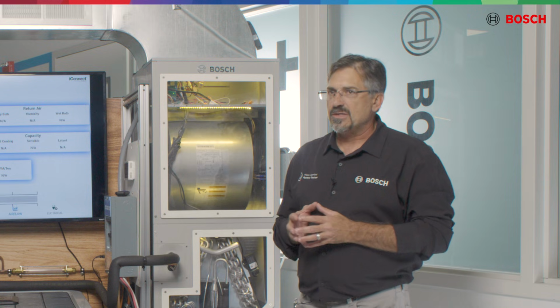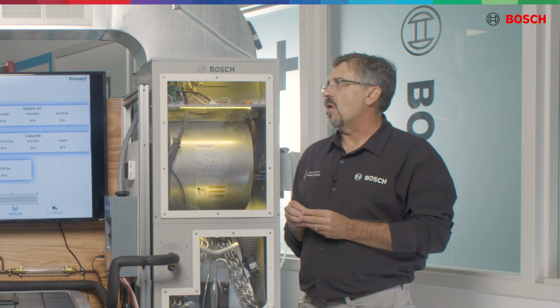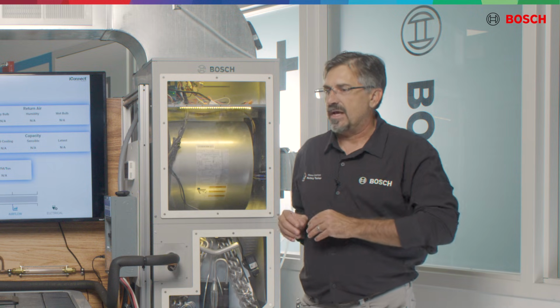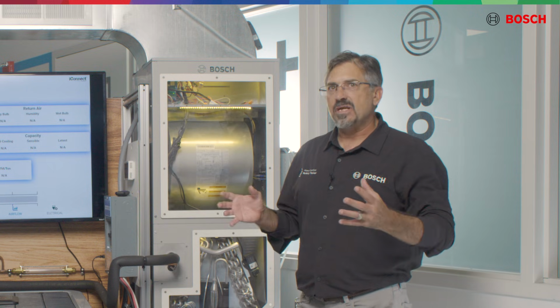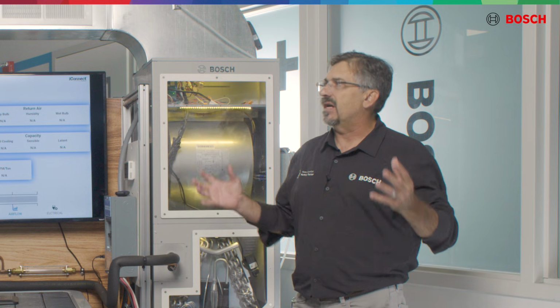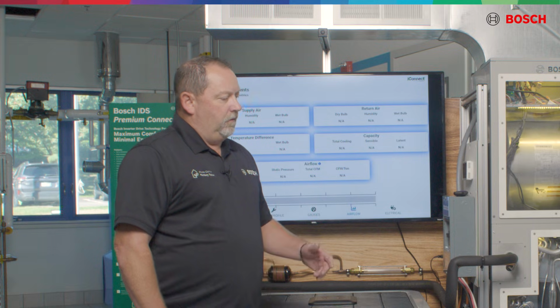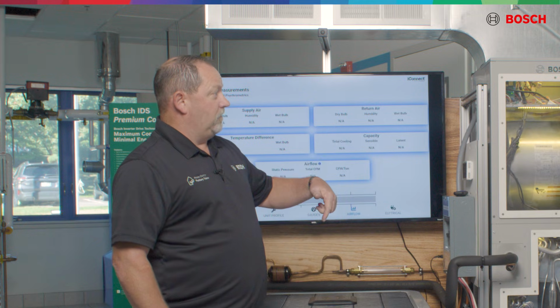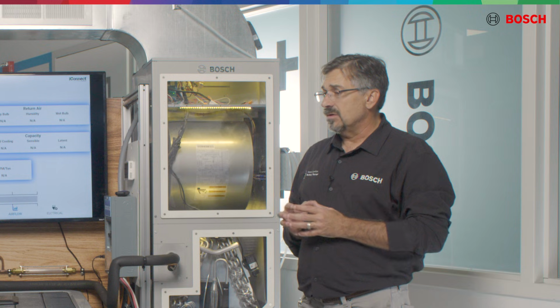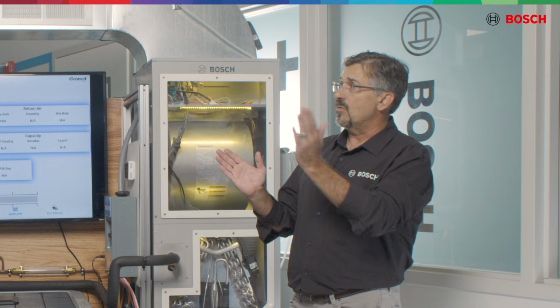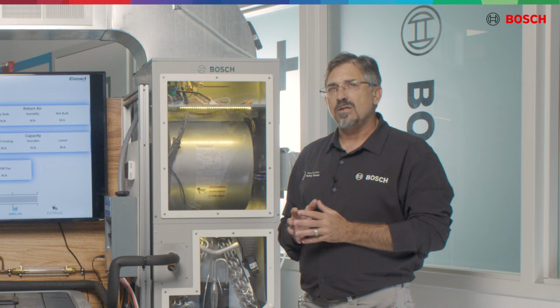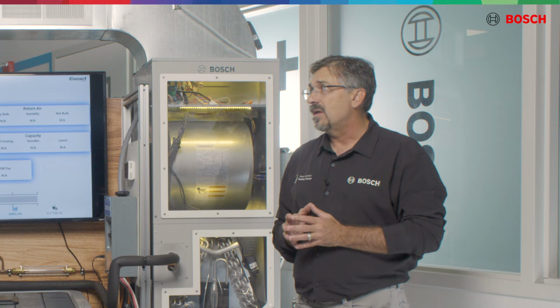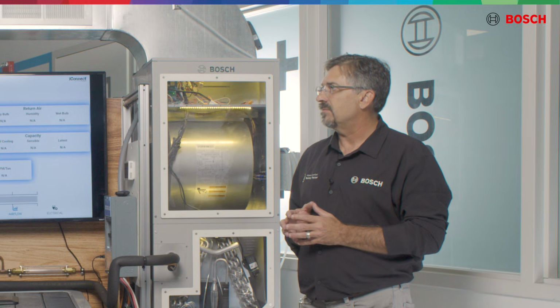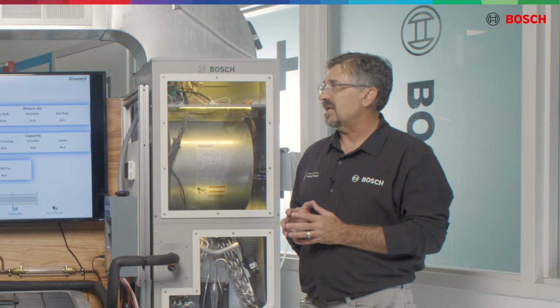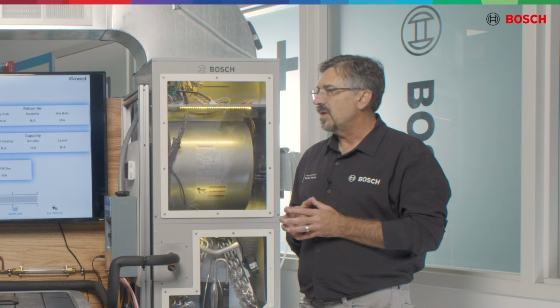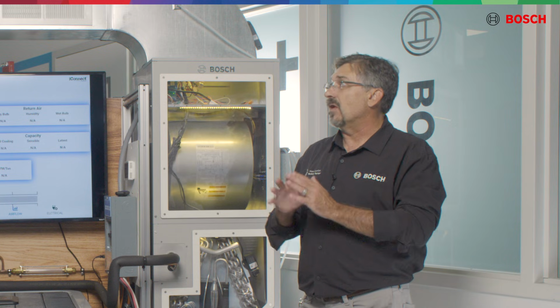Most of our fan motors and our Bosch equipment will top out at 0.8 inches of water column. That's total supply and return max. Anything over 0.8, our engineers have not designed a system to operate. It's outside of our engineering parameters. So the higher the static, the less the airflow. According to a set of gauges, your suction pressure is now lower than it needs to be. Most technicians, when they see low suction pressure, are going to add refrigerant. But they've overlooked one thing. If they don't pull out their manometer and look at the static pressure, we're going to overcharge a system. The problem with overcharging a system is that we've lost our capacity.